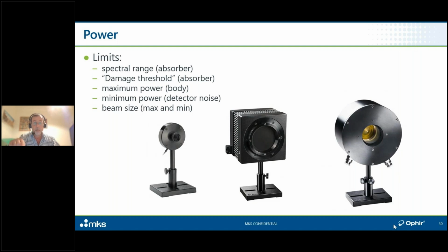We don't want to unknowingly cut off outer wings of the beam and get incorrectly low measurements and not even know about it. That's an effect that we call vignetting, unknowingly cutting off the outer bits of a beam because we thought that the beam was this big. But as a former colleague of mine once said, talking about the outer limits of a beam is kind of like talking about the outer limits of a cotton ball. It's not a clearly drawn line.